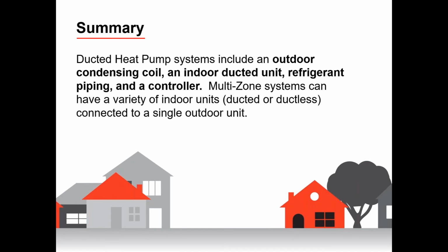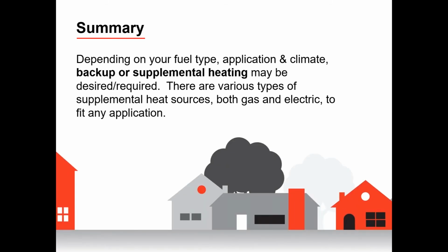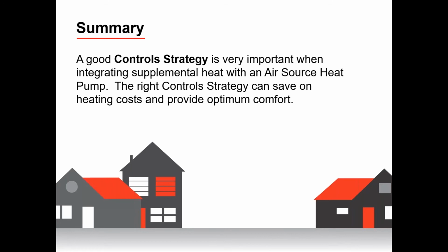Ducted heat pump systems include an outdoor condensing coil, an indoor ducted unit, refrigerant piping, and a controller. Multi-zone systems can have a variety of indoor units, ducted or ductless, connected to a single outdoor unit. So just remember those applications that we looked at with them. Depending on your fuel type, application, and climate, backup or supplemental heating may be desired or required, right? A lot of it may be desired. Like I said, if I'm putting in a fully ducted air handler, I'm going to put in that heat kit just as a desire, as peace of mind. It also may be required. If you're in Minnesota, if you're in northern Wisconsin, you're going to need backup or supplemental heat on an air source heat pump. There are various types of supplemental heat sources, both gas and electric, to fit any application. A good control strategy is very important when integrating supplemental heat with an air source heat pump.